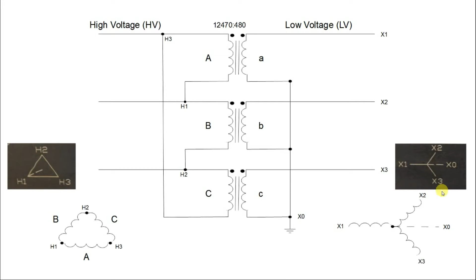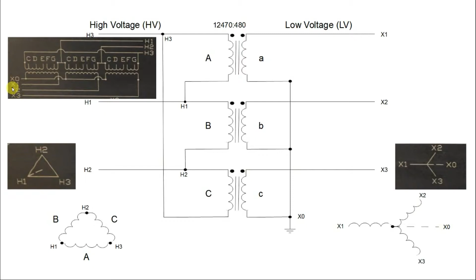This is a snippet from the nameplate showing the exact same thing. X1, 2, and 3 are in a Y configuration. This point here is electrically the same as this point here, so I'm just moving my labels out to the ends of the lines to clean them up. We'll look at a snippet of the nameplate that shows H1, 2, and 3 are the same points there. X0, which is my ground, is here, and X1, 2, and 3 are labeled right there.